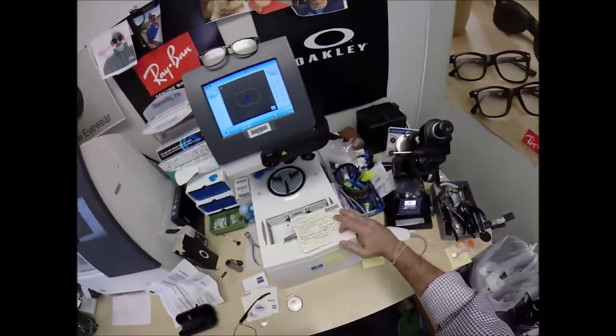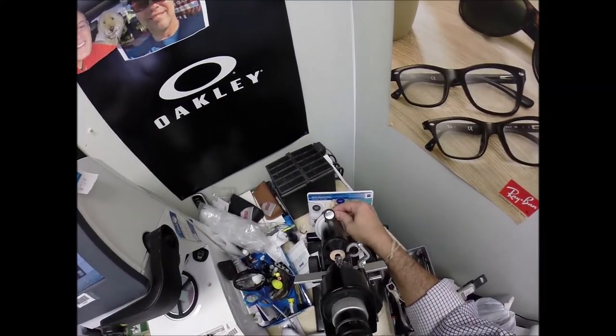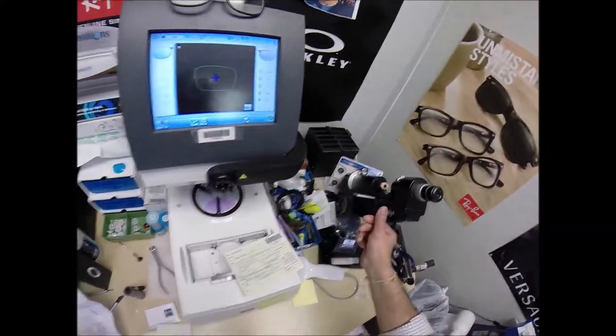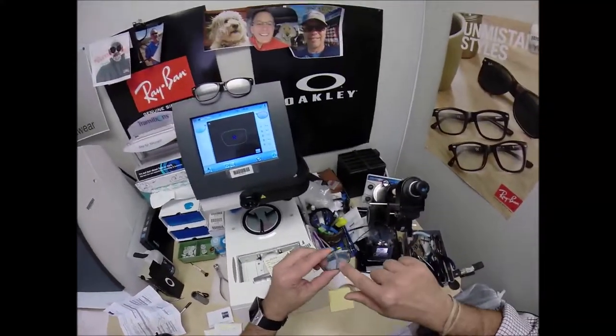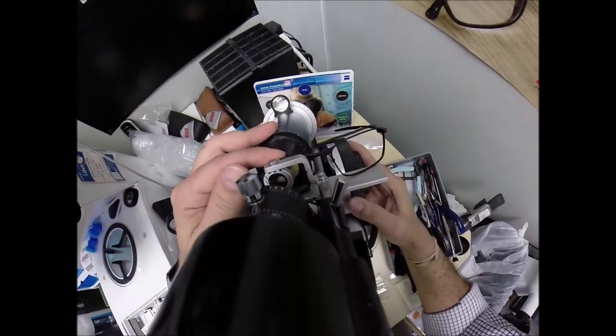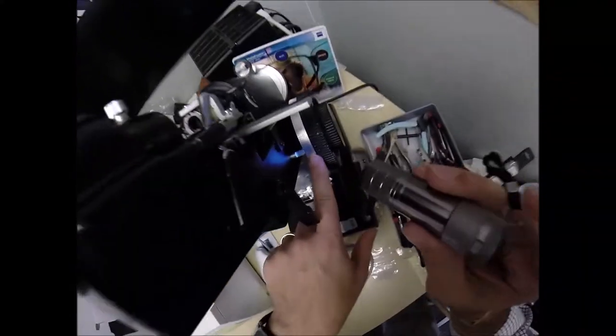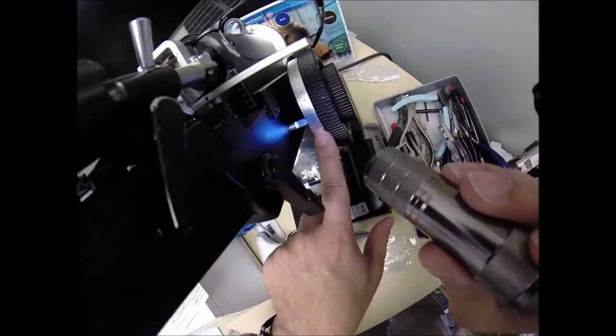So we're going to come down here to the lensometer, turn the axis wheel to 170, actually turn it on, put it in over that black dot, read the power, and I'm getting a hieroglyphic. No, I'm getting plus 3, exactly halfway between 2 and 4.